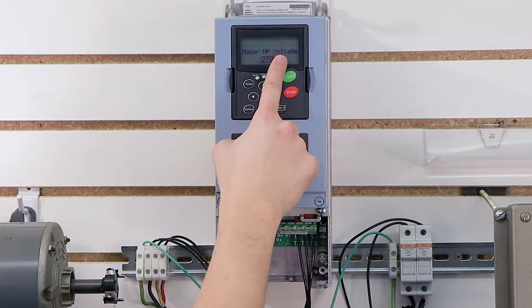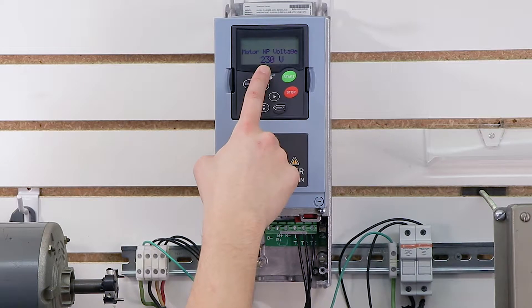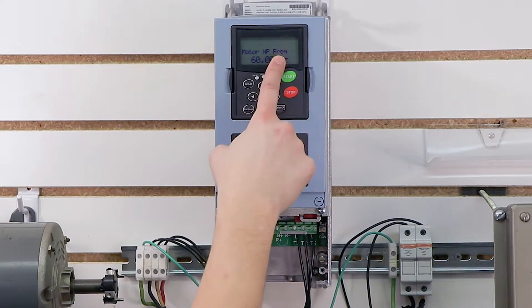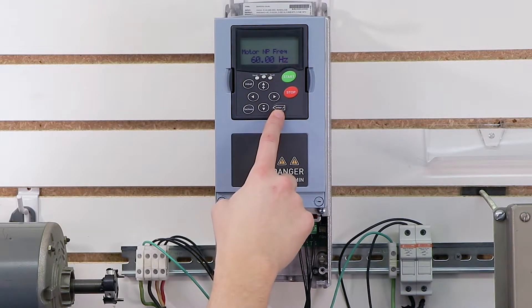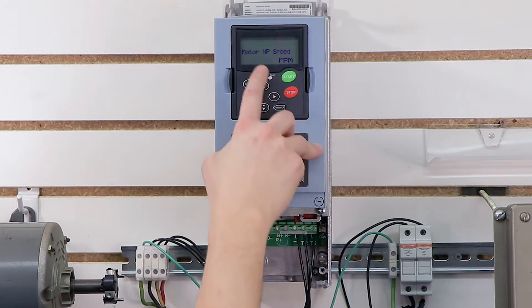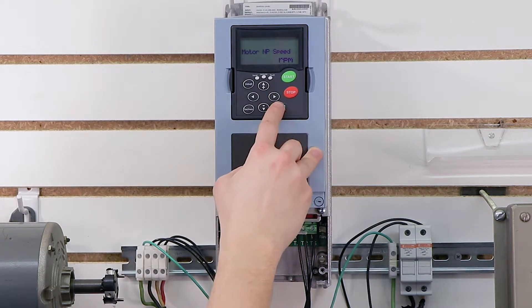My motor's nameplate voltage, I'm going to set at 230 volts. Again, that's what's on my nameplate. My motor's nameplate frequency, same. It's going to be 60 hertz. Again, that's on my nameplate. Motor's nameplate speed, 1720 RPM. That is also correct. I'm going to press enter again.